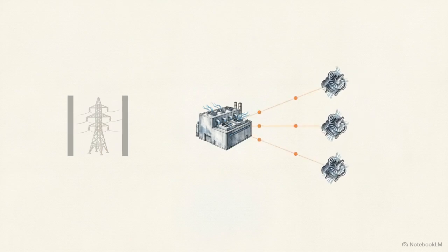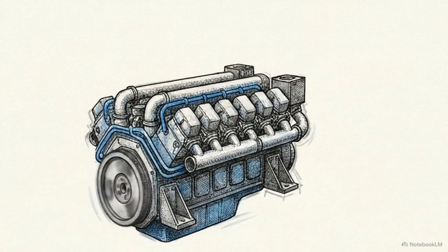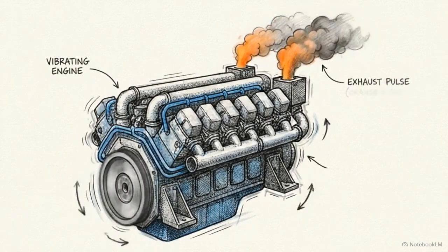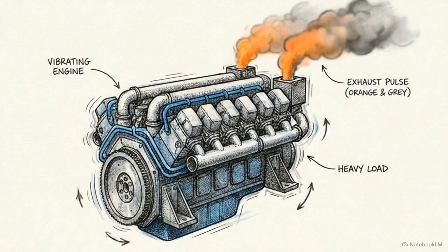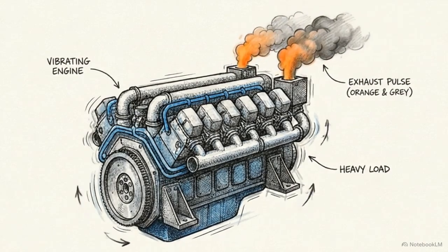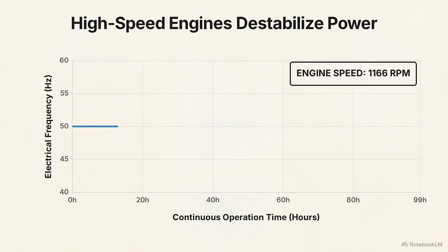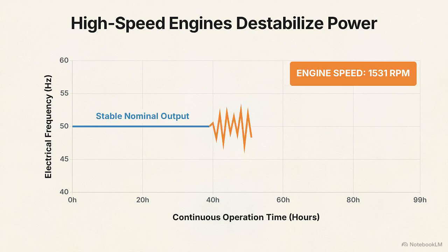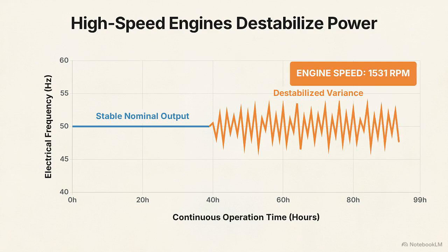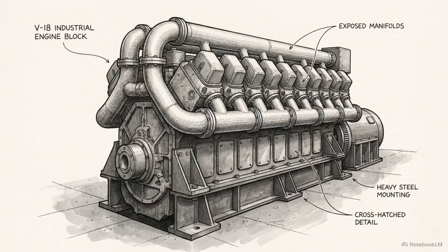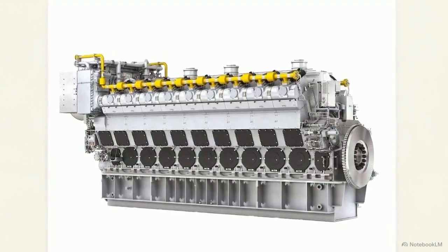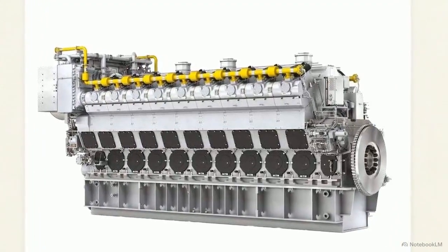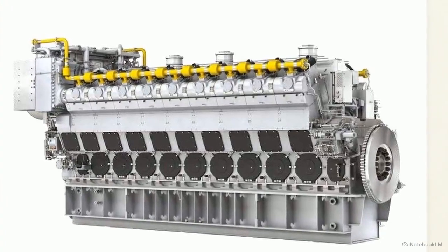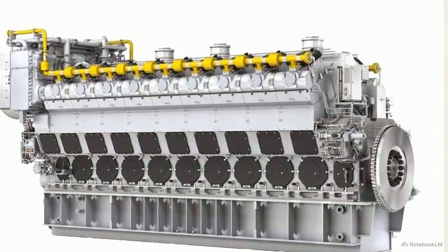Because external power is no longer guaranteed, operators are engineering these facilities as sovereign energy nodes, relying on dedicated on-site prime movers to maintain baseload capacity. While data centers have traditionally relied on high-speed emergency diesel generators, these units are not engineered for the demands of a primary captive plant. High-speed engines operating above 1500 RPM degrade rapidly under continuous baseload operation. The resulting voltage and frequency variances can destabilize or damage sensitive microelectronics.